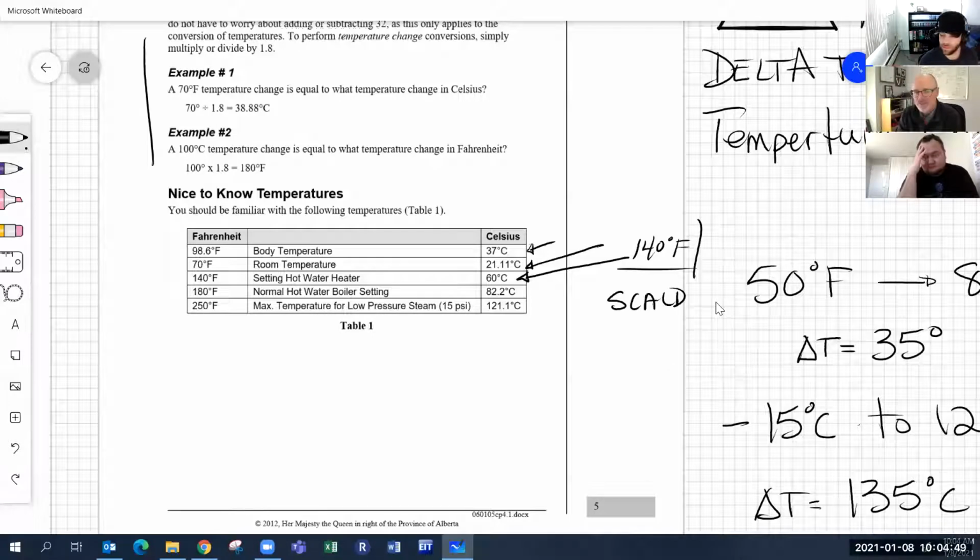Another reason is if we have temperatures less than 140 degrees and the water ceases to be moving. So say you go on vacation for 3 weeks and your hot water tank is sitting at 120 degrees, it has the opportunity to create bacteria inside that tank.